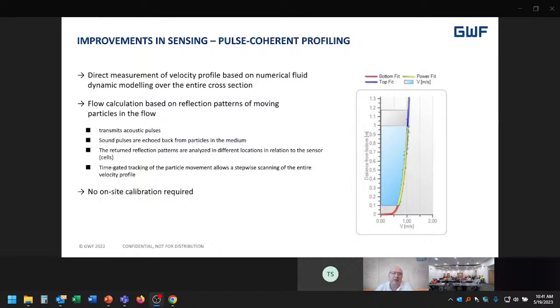So on the right here, we actually have a graph where you're seeing different heights within the channel. We're seeing different velocities. And I'll show a different example of this in a short while. So this means that we don't need to calibrate on site. We can tell the systems what the shape of the channel is, but we're then starting to track particle movement and actually measure the velocity profile and not just one point within the medium.